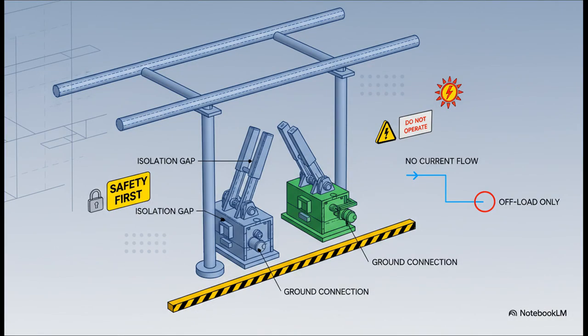Now, isolators and earth switches. These are all about one thing, safety for the people doing the work. They are used to create a clear, visible air gap in a circuit, physically disconnecting it. Then the earth switch connects it to the ground. This guarantees a piece of equipment is totally de-energized and safe to touch. But here's the critical part. You can never open these when current is flowing.